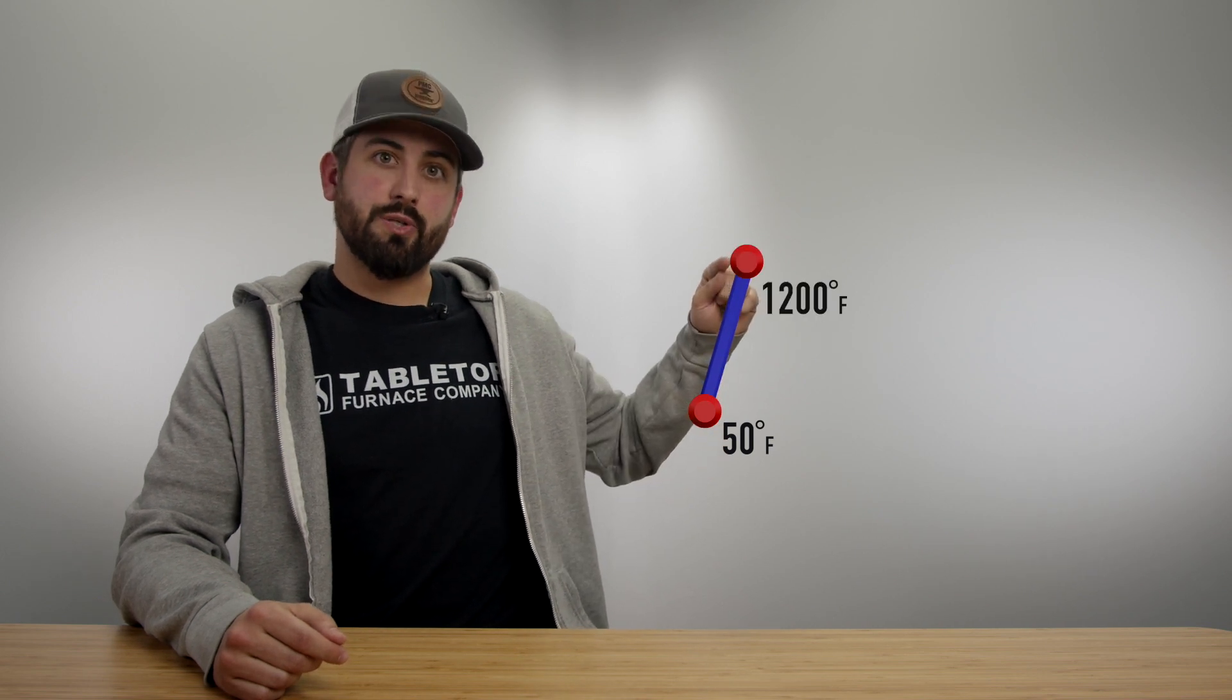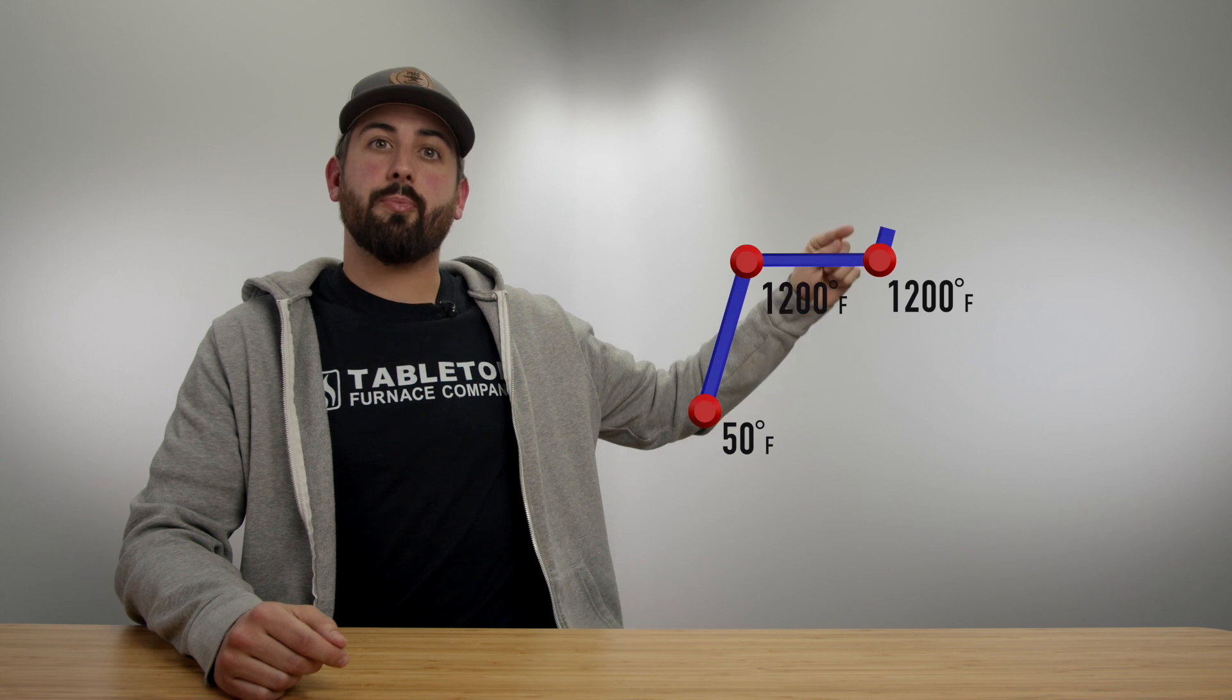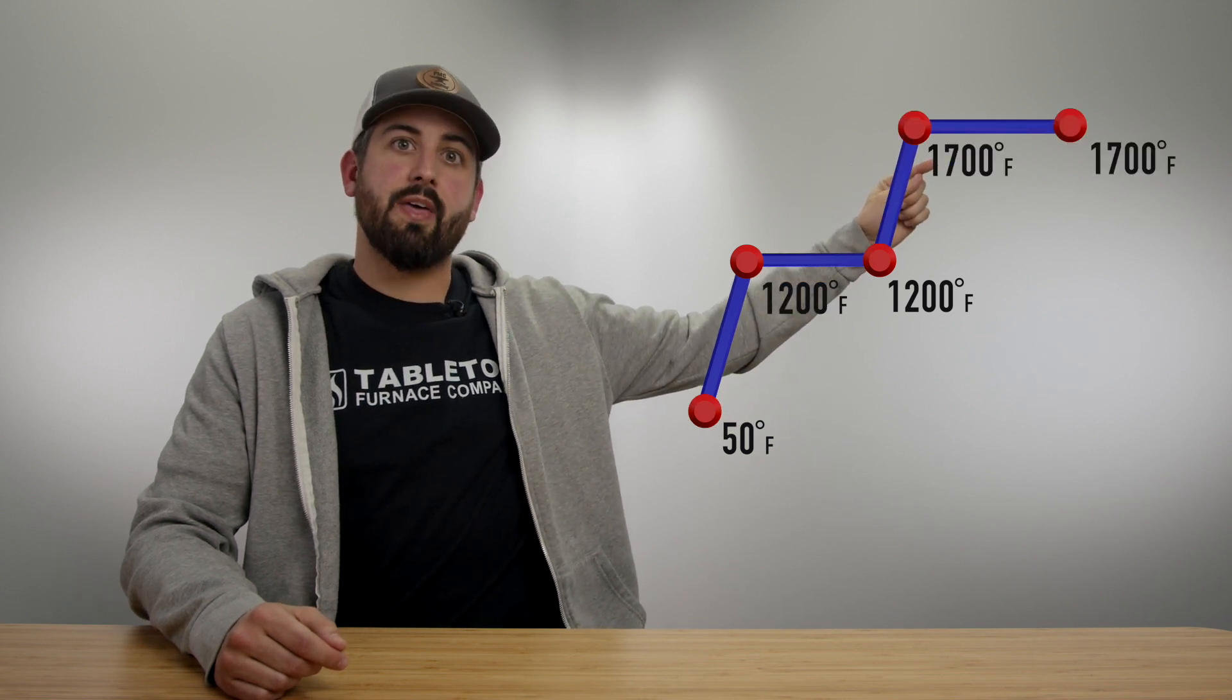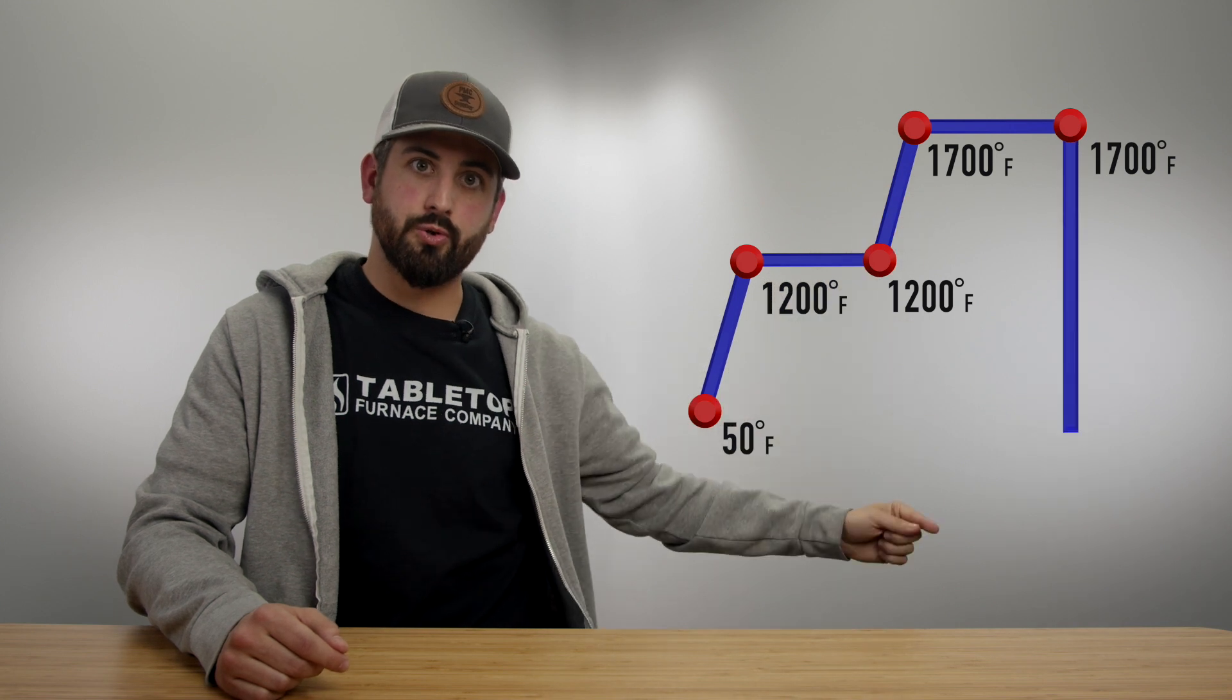Your burn-off schedule is going to look something like this. We're going to have a start temperature. We're going to rise up to our first target temperature at which point we're going to hold, then we're going to rise up again to another temperature. We're going to hold there again for a little while and then when we're all finished we're going to cool down naturally.